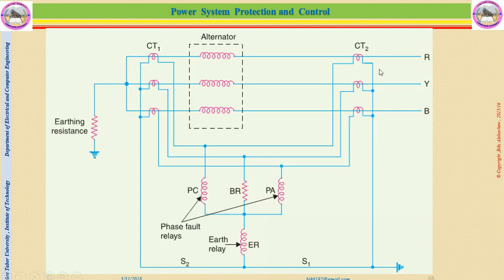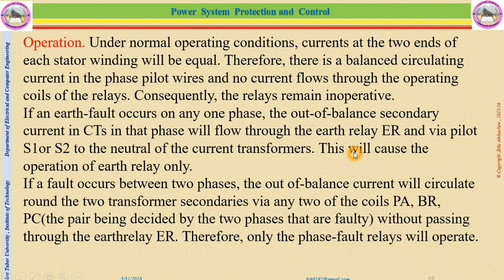That means if the fault is between R and Y, the current will circulate in BR and PC. If the fault is between Y and B, the current will circulate in PA and BR. And if the fault is between R and B, the current may circulate in PA and PC. So the path of this circulation depends on the faulted phases. But remember, this fault does not pass through the earth relay. Therefore, only the phase fault relays will operate in these phase fault conditions.